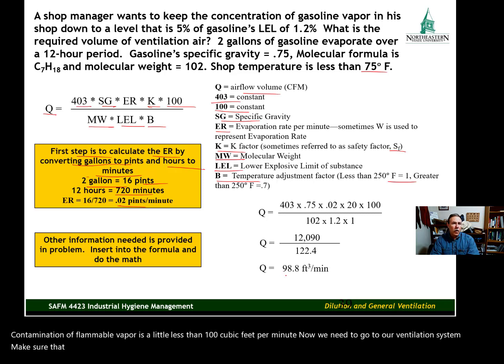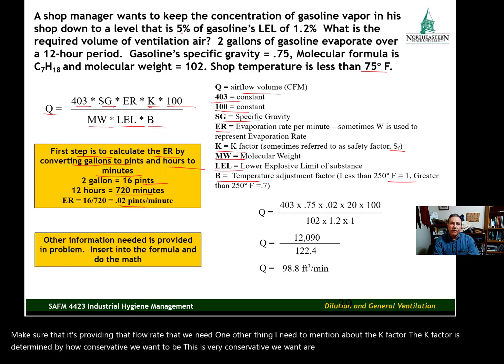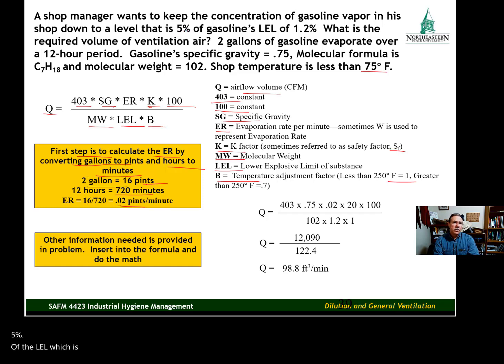One other thing I need to mention about the K factor. The K factor is determined by how conservative we want to be. This is very conservative—we want our flammable vapor concentration to be 5% of the LEL, which is very conservative. It could be 50% of the LEL and that would still probably be satisfactory as far as avoiding the potential for flammable vapors to be ignited.